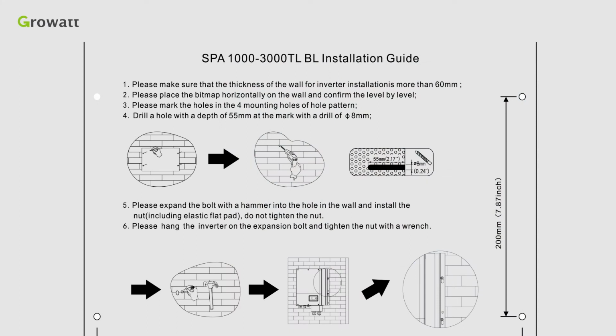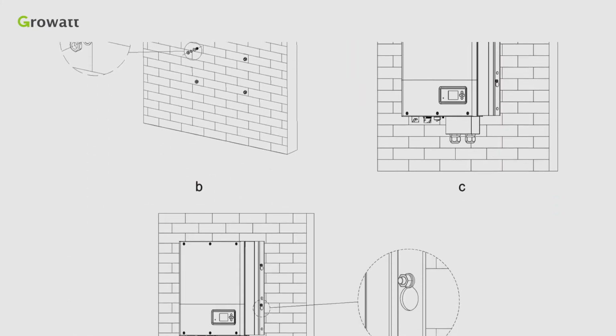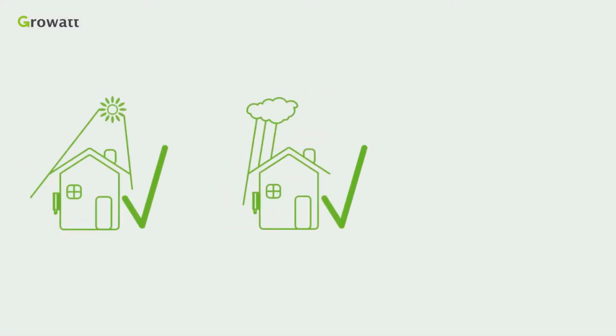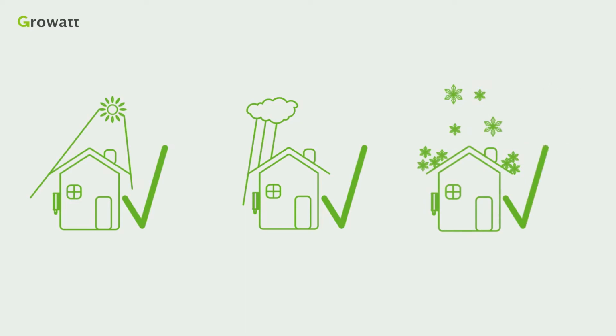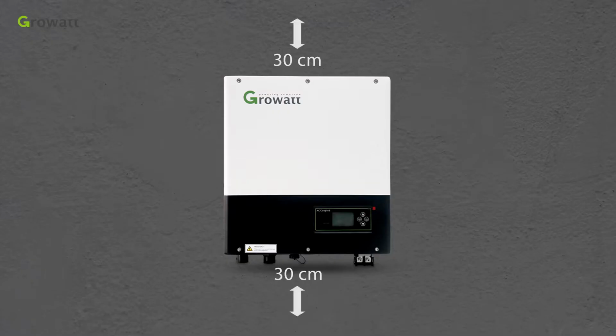Follow the location requirement in the manual to install the inverter in a proper place. It is suggested to install the inverter under a shelter, avoiding direct sunlight and rain. The wall should be stable. Airtight cabinet is prohibited.